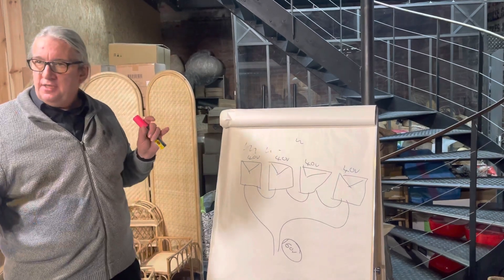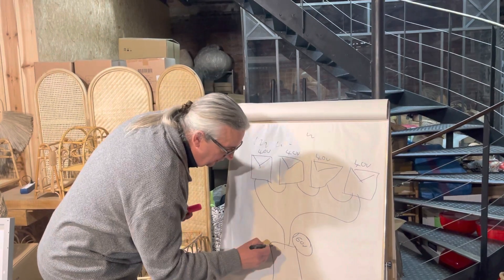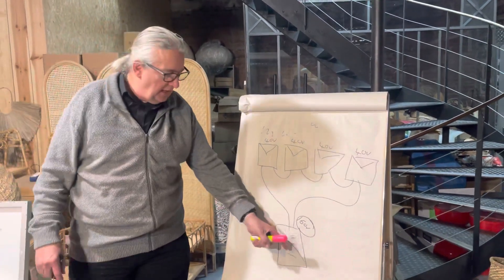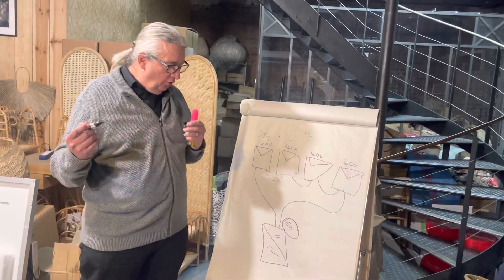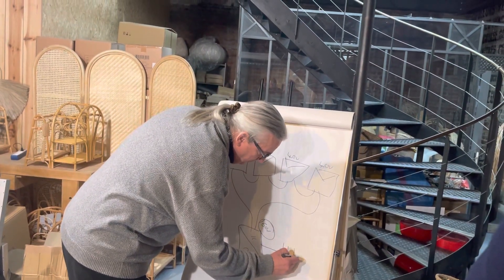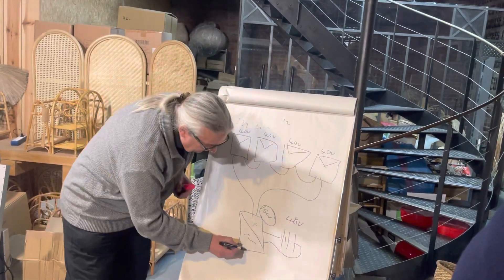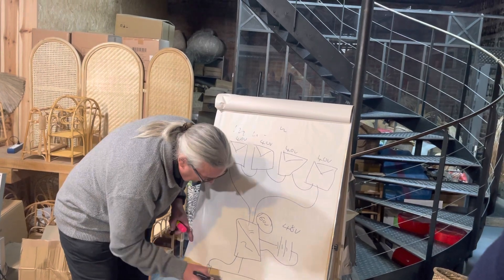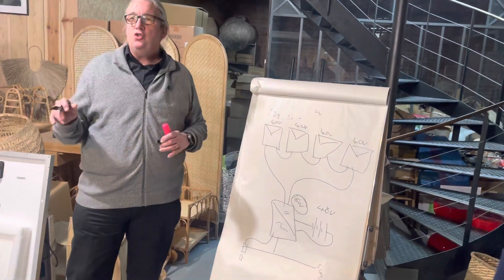You may need more panels, but very simply they're in series. The panels connect to the inverter — this is the symbol for an inverter, DC and AC. Our inverter also connects to a battery at 48 volts. Then here it connects to your grid, here we put in the CT coil, and here is my load — these are non-essential loads in normal circumstances.